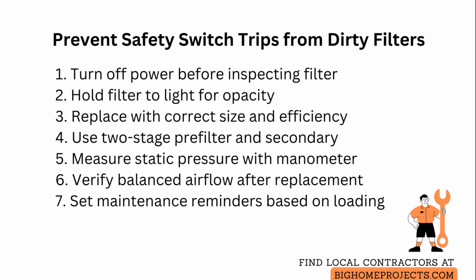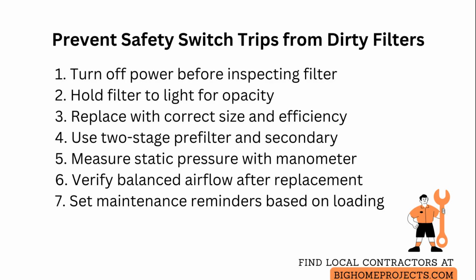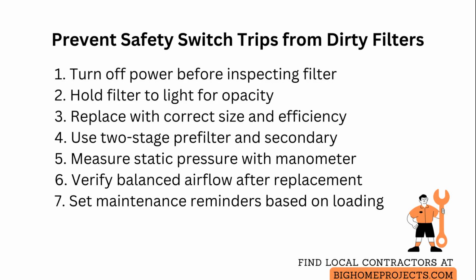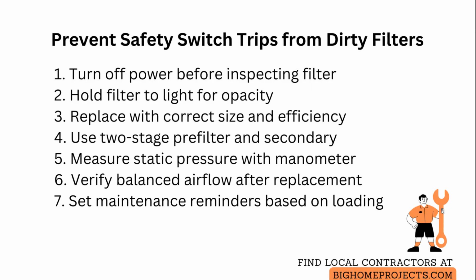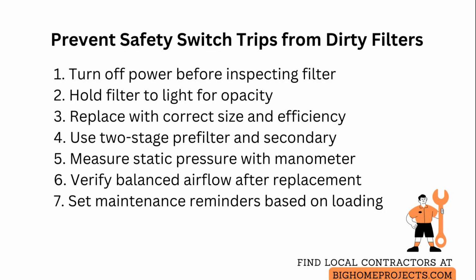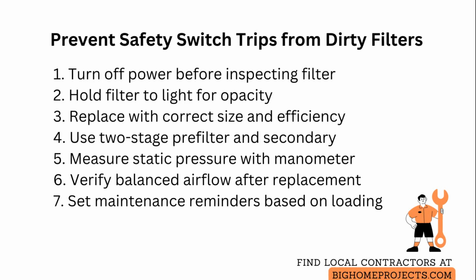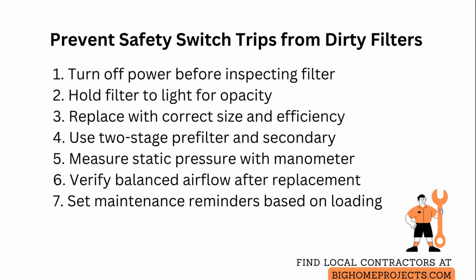Where particulate load is high, consider a two-stage approach with a washable pre-filter and a disposable secondary. Measure static pressure across the filter slot with a manometer if you have one to compare to manufacturer limits, and verify after replacement that supply and return vents are delivering balanced airflow by hand or with a simple flow hood reading.